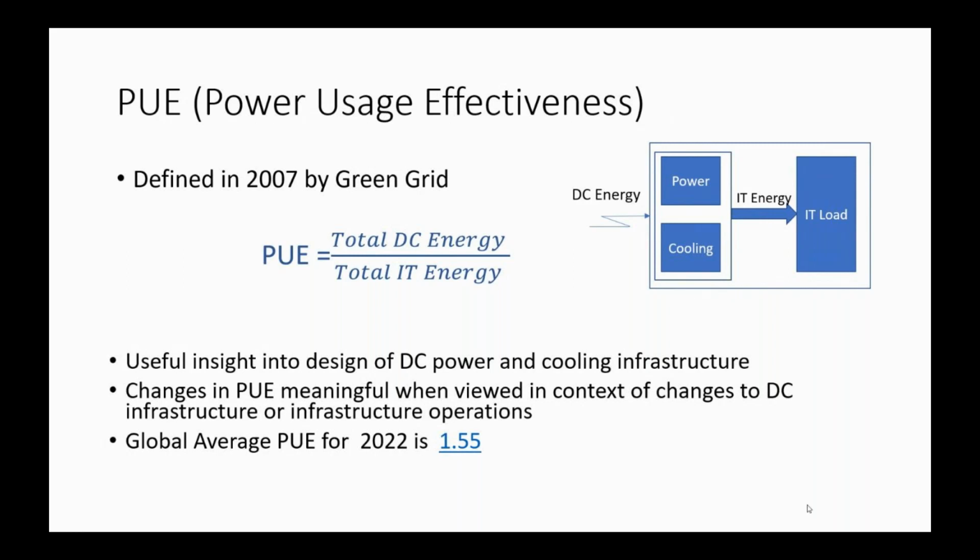So essentially, how much are you wasting in your power delivery, and how much is your cooling costing you, right? If you change those two, then you're influencing PUE in a meaningful way, because the ideal you want to get to is every kilowatt hour of energy that's coming in, if it's going to IT, essentially you get to one.